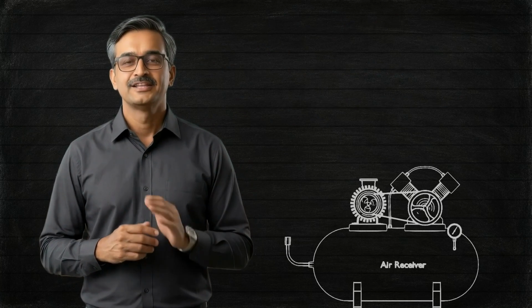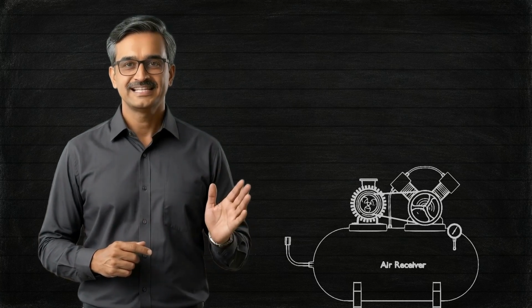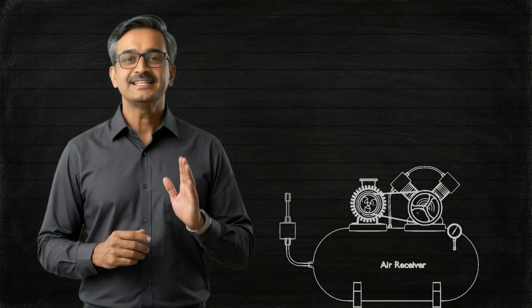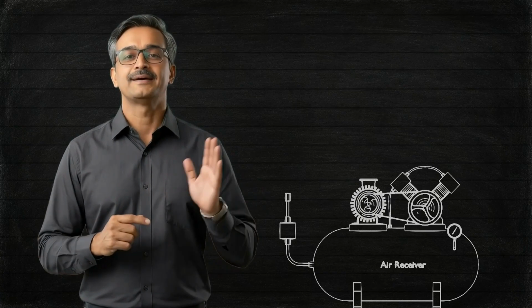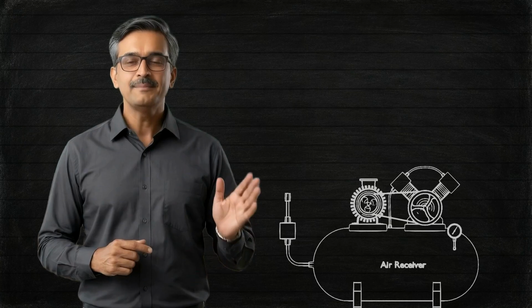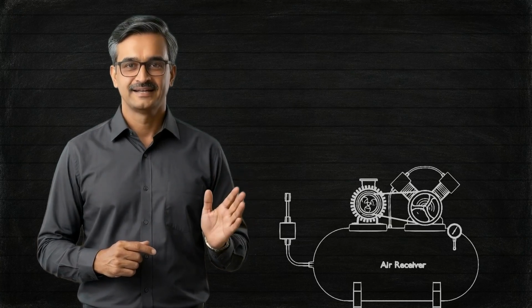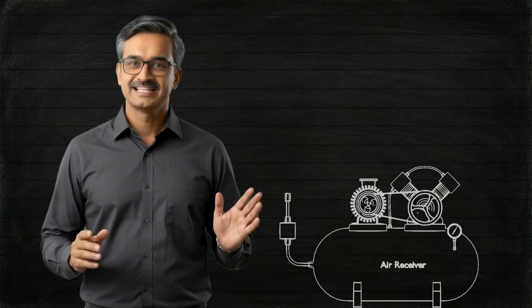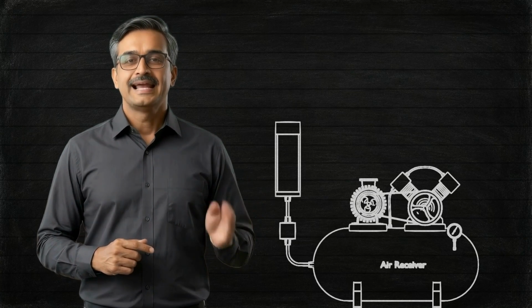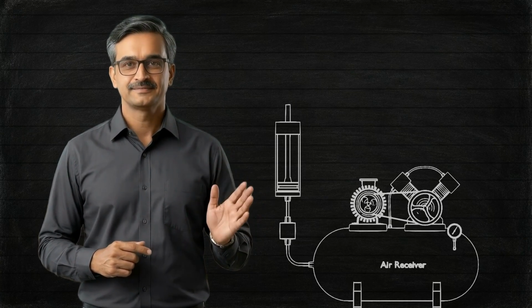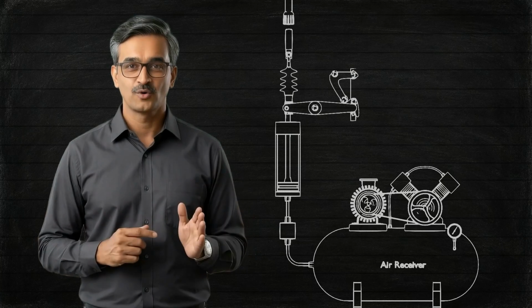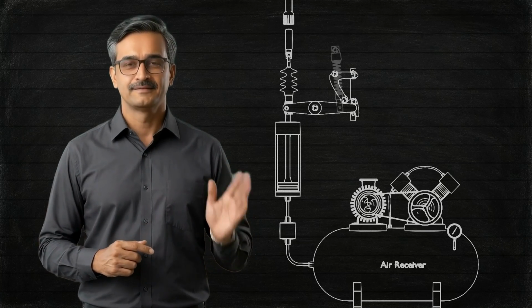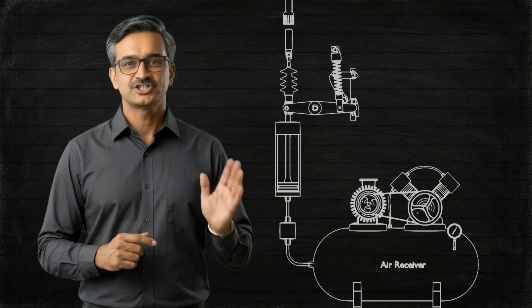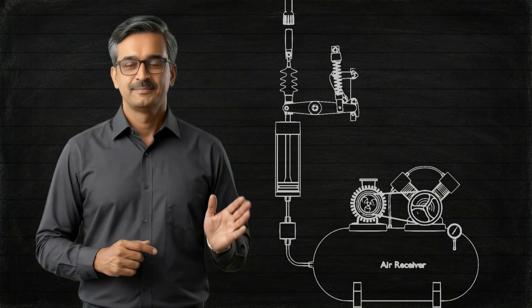This is simply a storage tank. Inside this tank, compressed air is stored at high pressure. This is the solenoid-operated pneumatic valve attached to the outlet pipeline. From the valve, there is another pipe leading to a pneumatic cylinder. Inside the cylinder, this is a piston. The piston rod connects to the operating linkage of the circuit breaker. There is a spring beside the linkage. This is the opening spring.